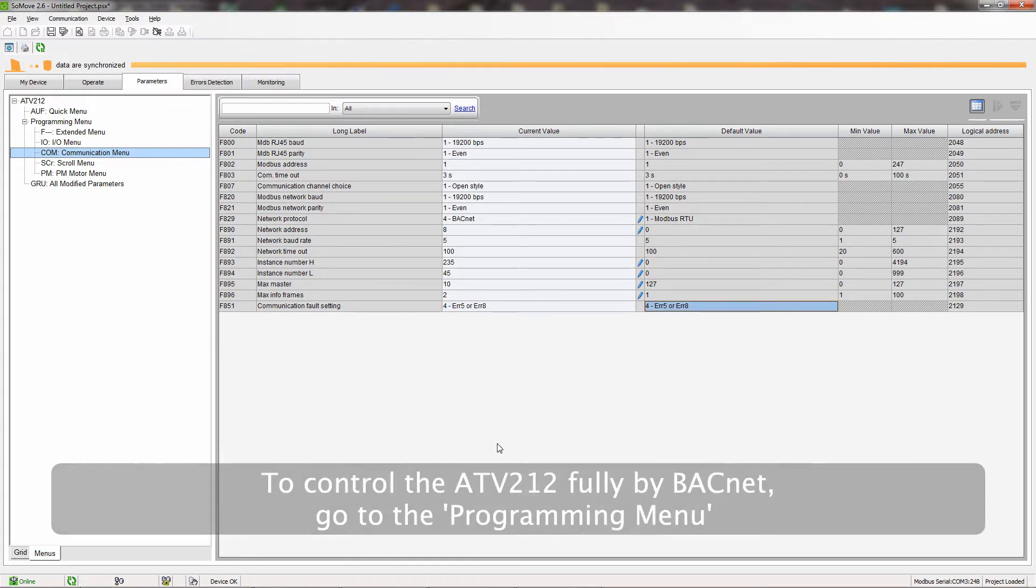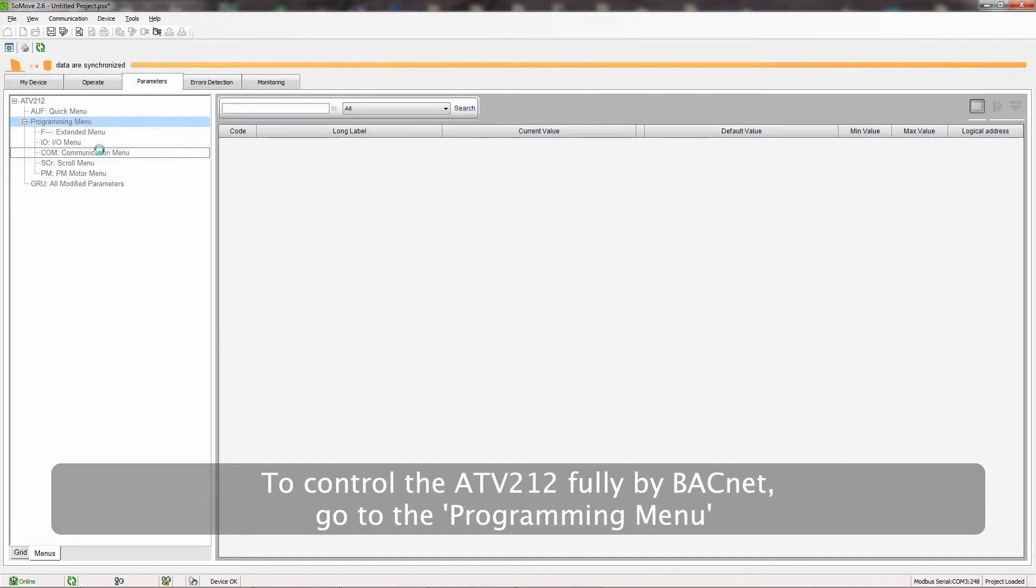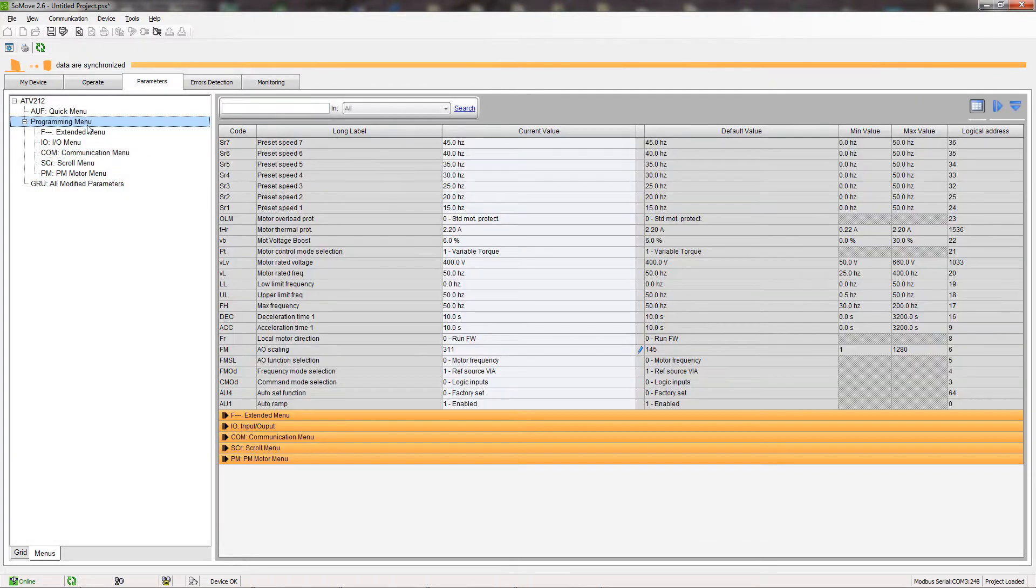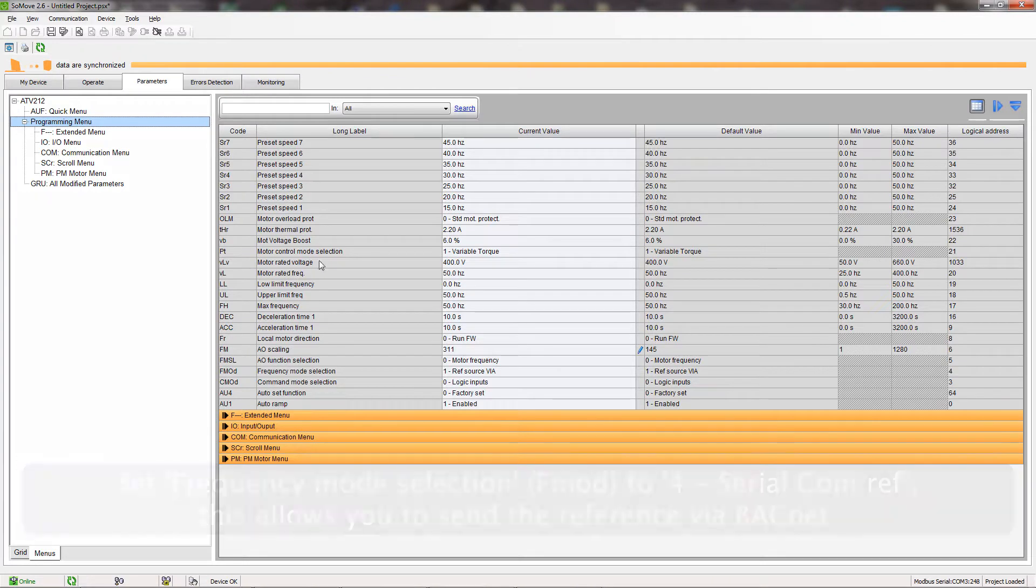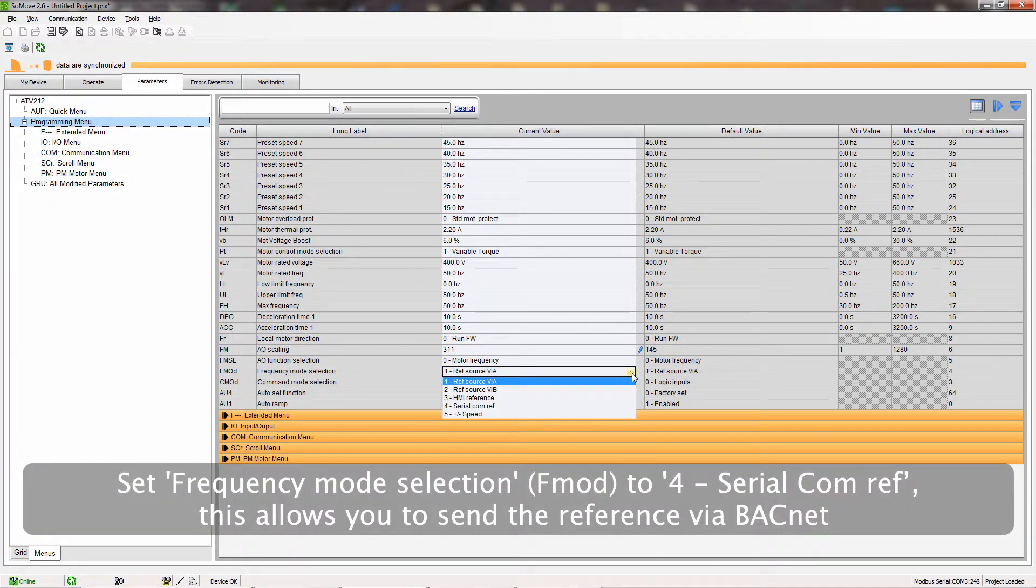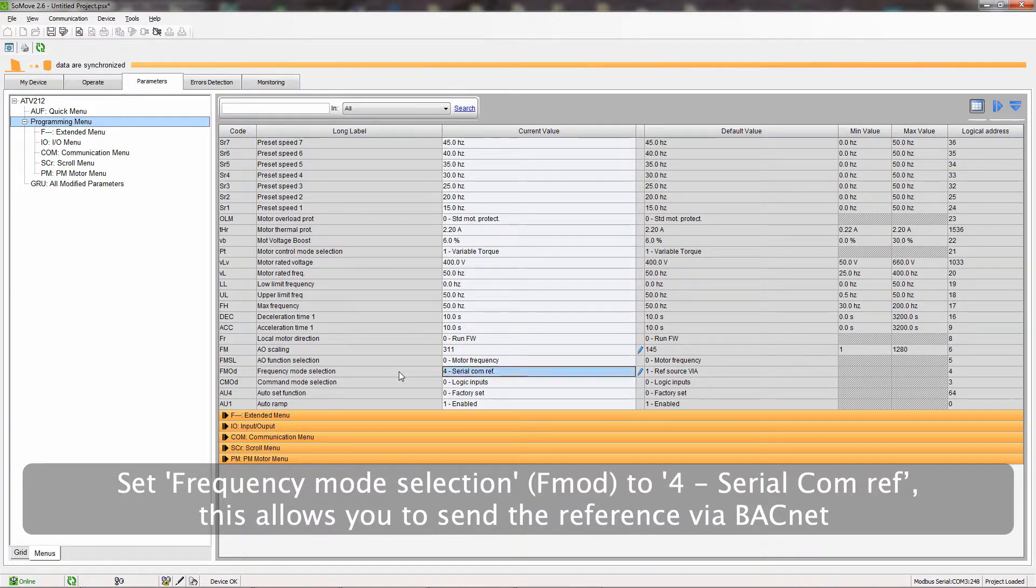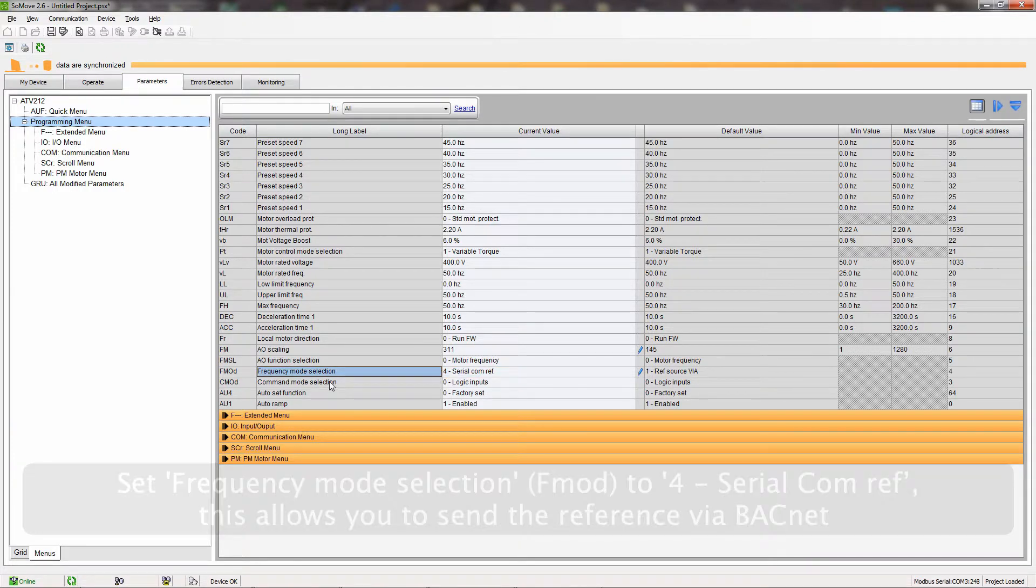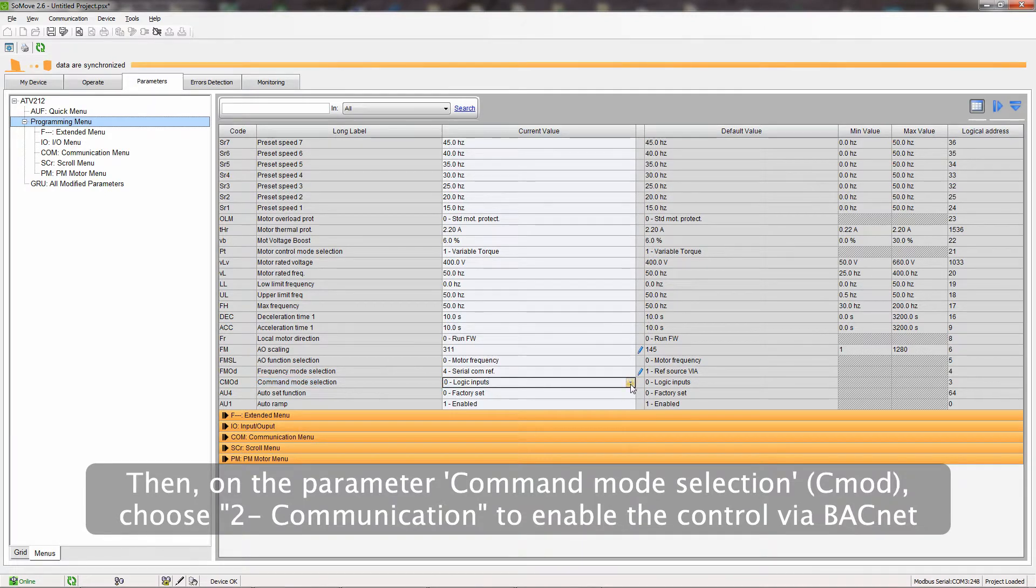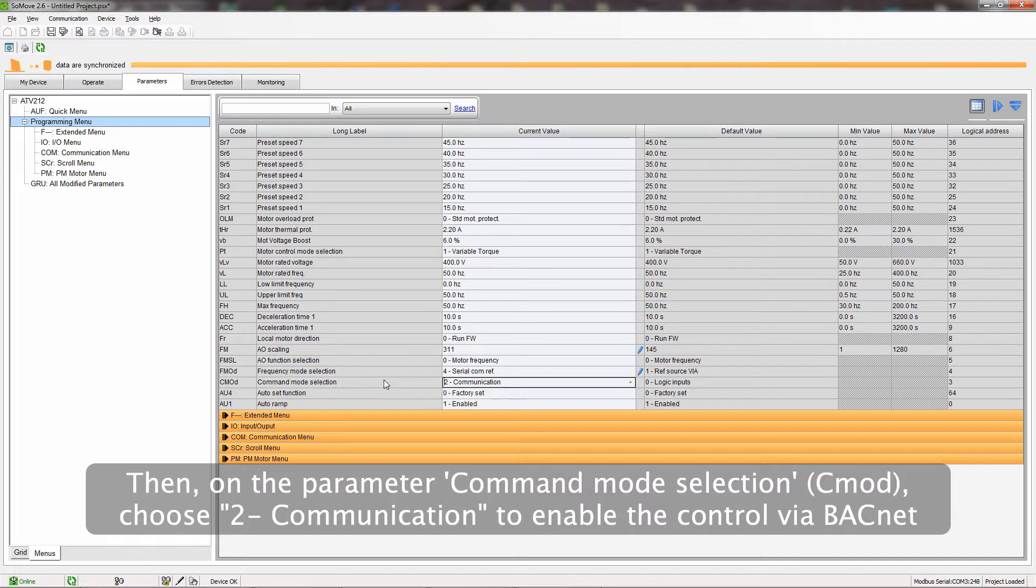To control the ATV212 fully by BACnet, go to the Programming menu. Set Frequency Mode Selection to 4 - Serial Com Ref. This allows you to send the reference via BACnet. Then, on the parameter Command Mode Selection, choose 2 - Communication to enable the control via BACnet.